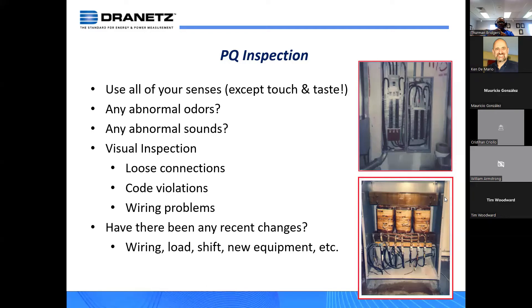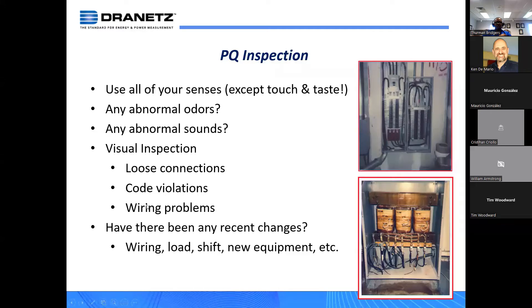For the inspection, use all your senses but don't touch. Look for abnormal odors, abnormal sounds, and do a visual inspection. Loose connections are notorious, and code violations are also notorious — for example, illegal loops to the ground bonds can cause havoc, and ground loops. What I've seen particularly with a new facility experiencing PQ problems is that the visual inspection usually reveals where the problem is. It's not necessarily something failing — it's the loose connections, code violations, wiring problems, and miswiring. With new installations or retrofits, pay particular attention to the visual inspection stage.